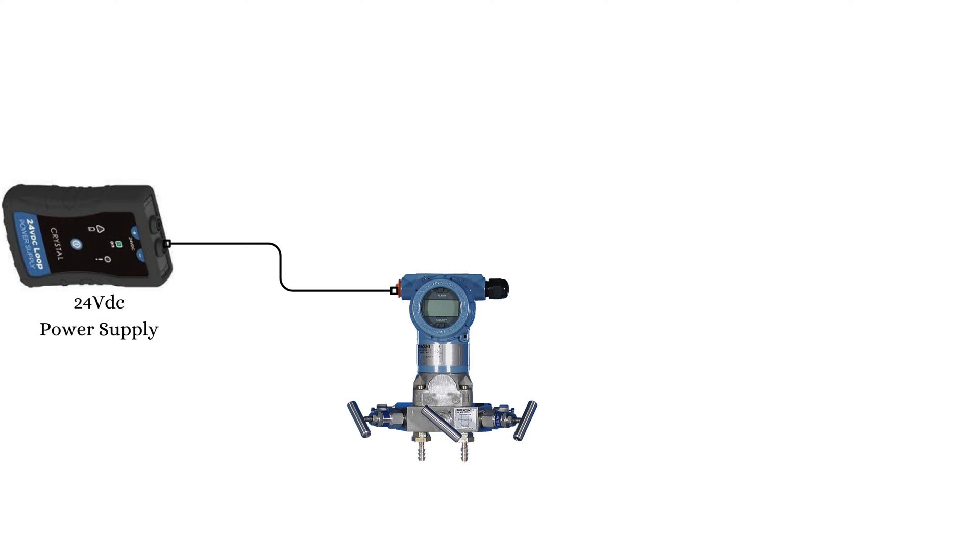If the differential pressure flow transmitter is in the field, then isolate the DP transmitter. Flush the differential pressure transmitter in a closed drain if it comes into contact with a dangerous process medium like a hazardous chemical.